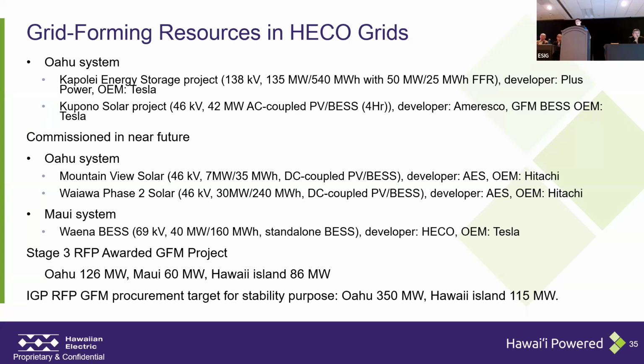And then on Maui, we will have our first transmission connected grid forming project in a couple of years. It's a standalone battery, 4 hours, and 40 megawatt. The OEM is also Tesla, and it is developed by HECO. Right now we're wrapping up the stage 3 RFP system impact study. In this RFP activity, I think we procured 126 megawatt of IBR projects for Oahu. All of them are grid forming projects, PV paired with battery, AC coupled, and Maui 60 megawatt, the same PV paired with battery, one AC and one DC coupled.